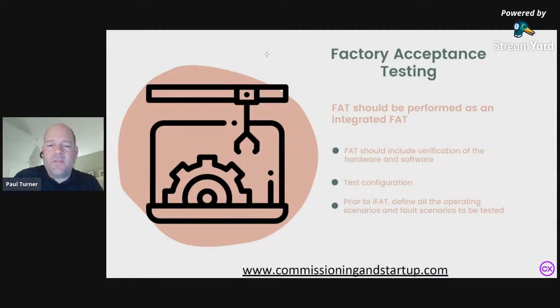Once your hardware arrives at site and it's installed, that's all great, but your software still hasn't been proven to work, and it's delayed much later in the process. By the time all your hardware is shipped, and by the time you've got software that's ready to be tested, that's much later in the project, and you're really completing your software design as you're trying to do commissioning. That never goes well.